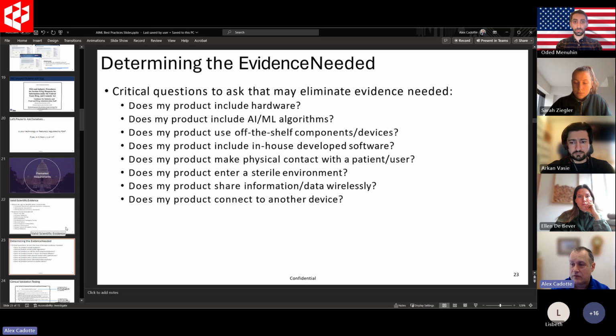Does my product share information and data wirelessly? Basically, if your device has software, you're going to have to do cybersecurity these days. So FDA is pretty tough on this. Like, if you try to avoid cybersecurity regulation by saying, oh, my device is locked down, it doesn't communicate with anybody, sorry, you still have to do cybersecurity if it has any ability, when it's being developed or when it's being used, to access the software. And I don't want to give you any hope that you can get around cybersecurity. You're going to have to do it, is basically my message there, if you have software as part of your device, and firmware is included as part of software.